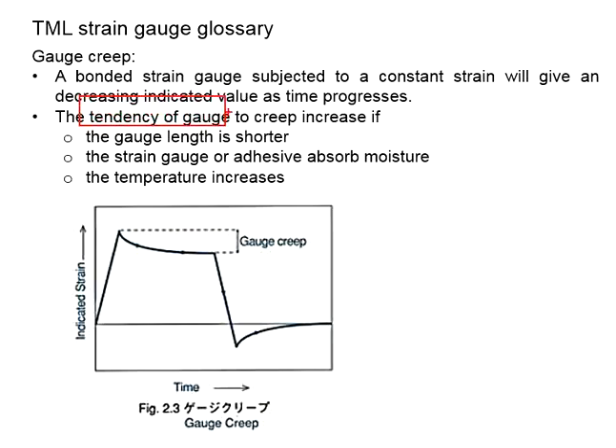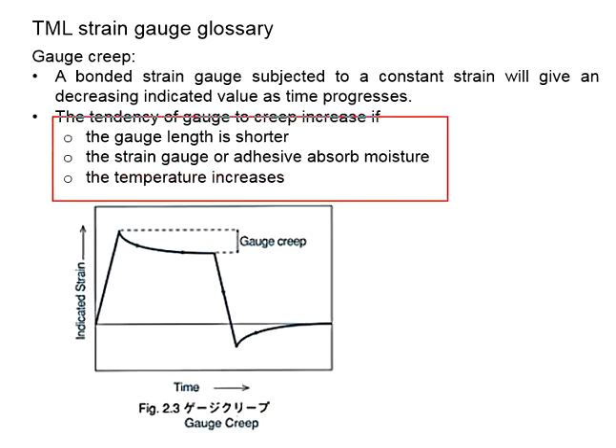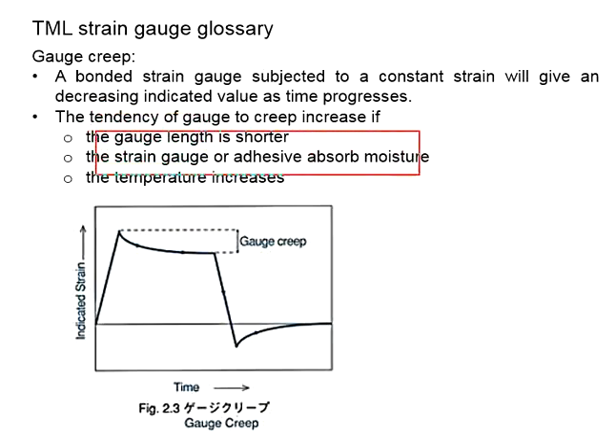The tendency of the gauge to creep increases if the gauge length is shorter, or if the strain gauge or adhesive absorbs moisture, or if the temperature increases. If you need to measure the strain of the specimen which is likely to be held constant over a period of time, probably you can take this into consideration. Use longer gauge length, do proper protection for moisture, and ensure the temperature is not an issue with the testing.